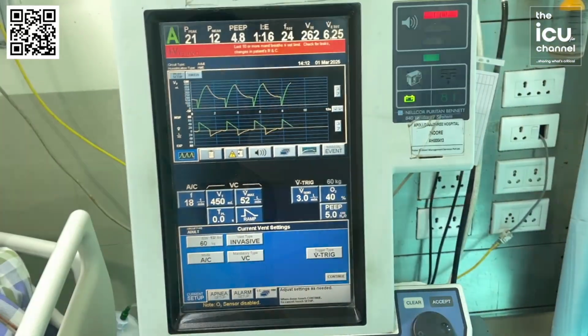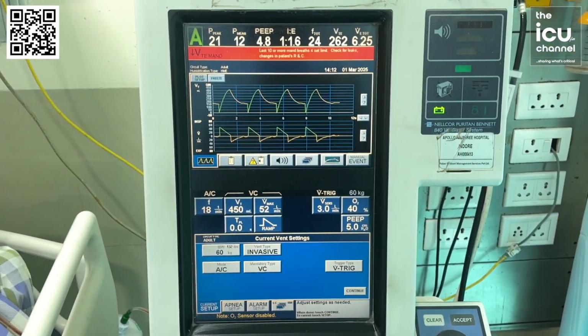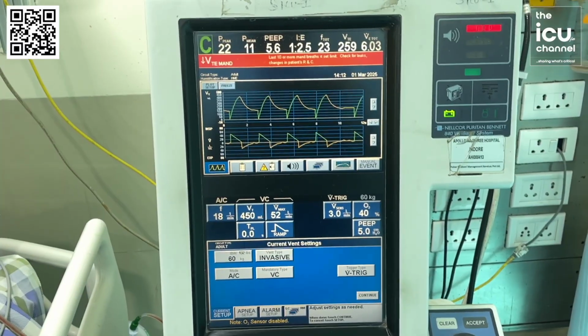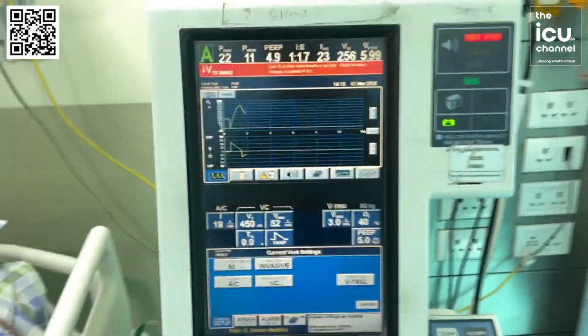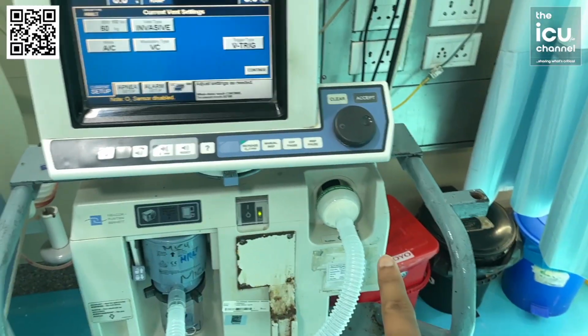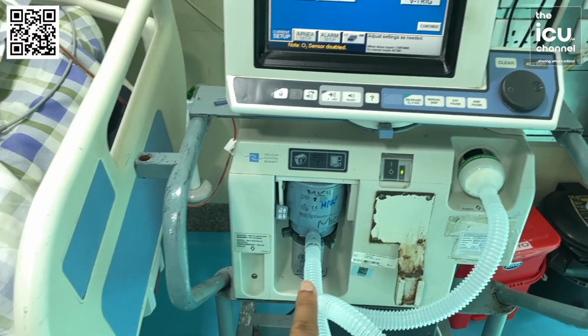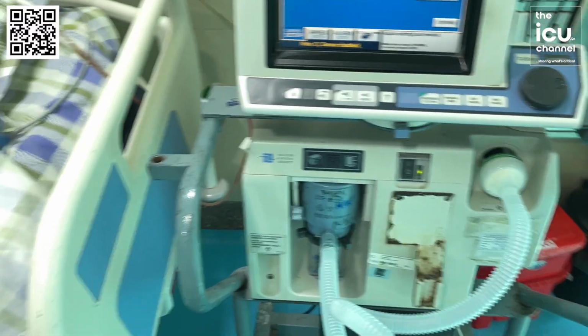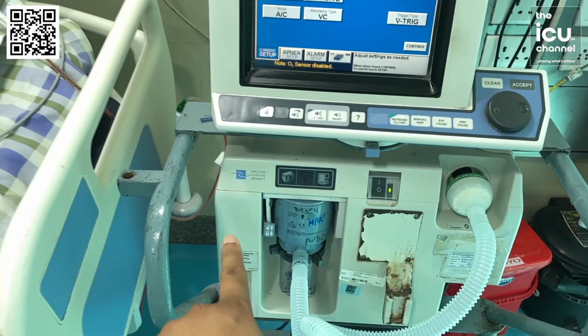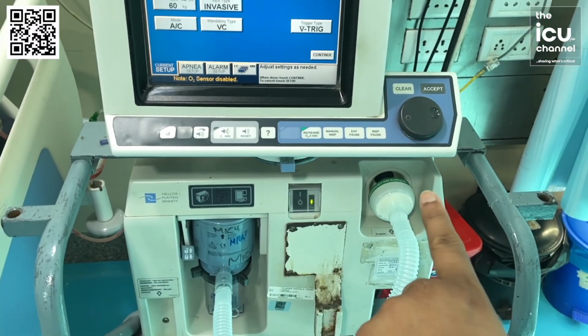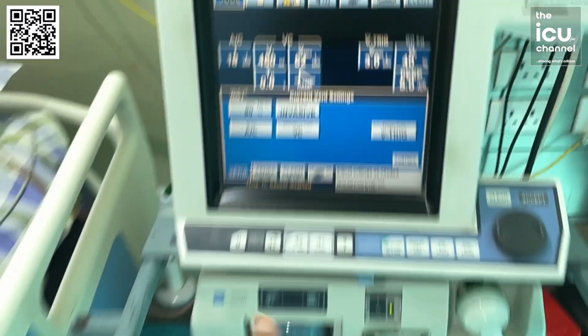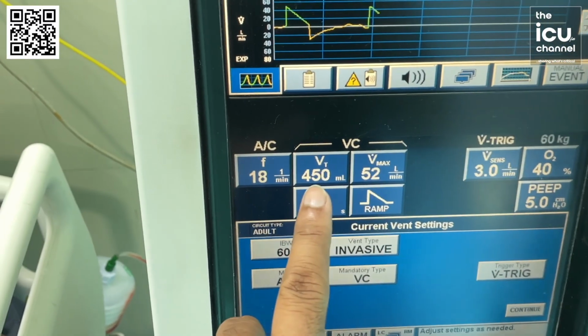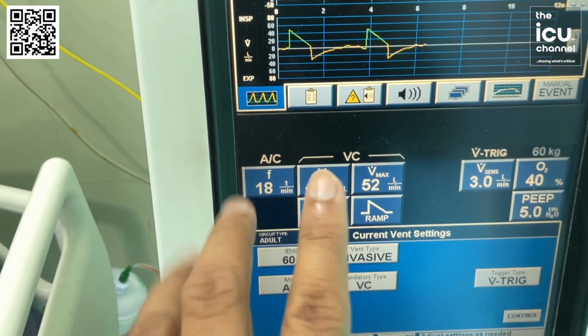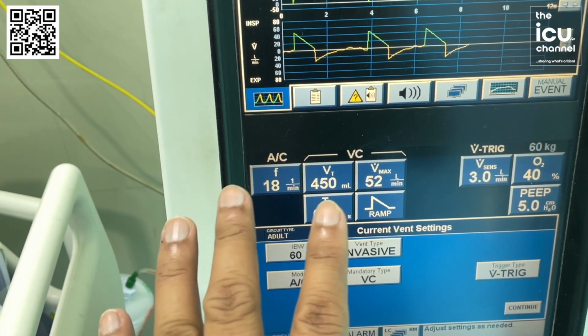So this is an example to demonstrate what we have just understood on the ventilatory circuit. This is the inspiratory limb, and this is the expiratory limb. This is going to the patient, and this is coming back from the patient. This is the filter and the flow sensor, the flow sensor on the inspiratory limb on the inside. We have set the tidal volume 450. So ideally, we should deliver the 450 tidal volume, and the same should be sensed in the expiratory flow sensor.